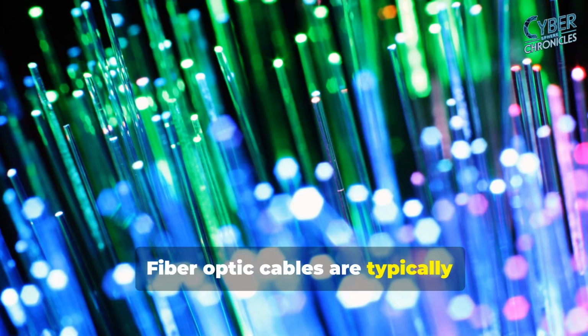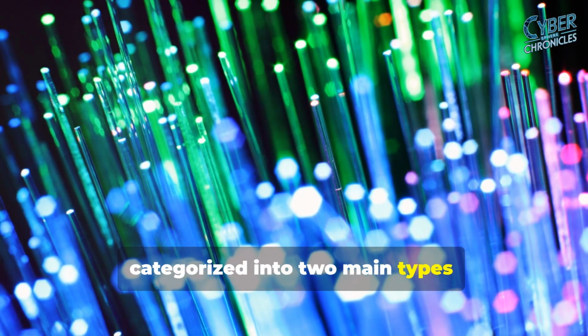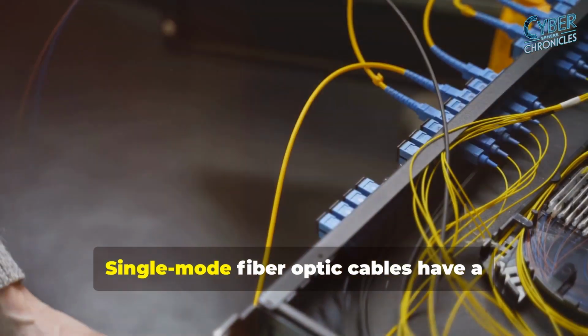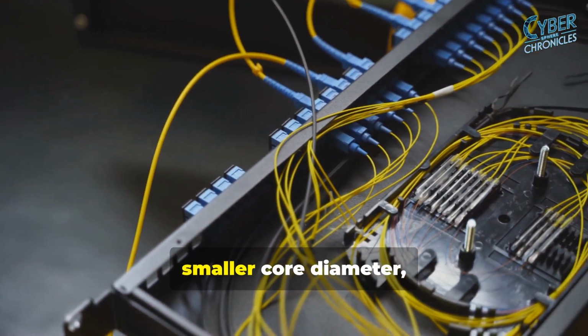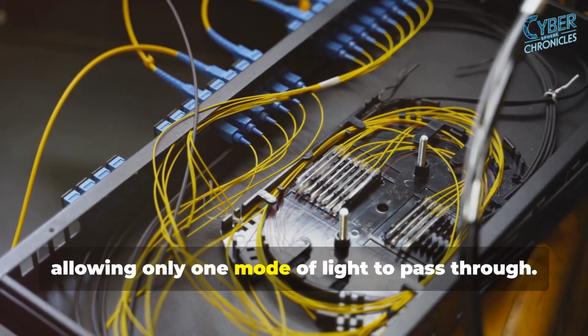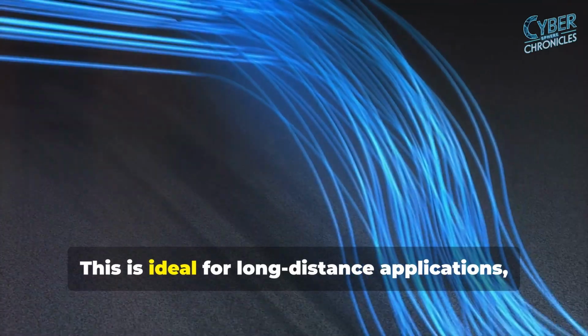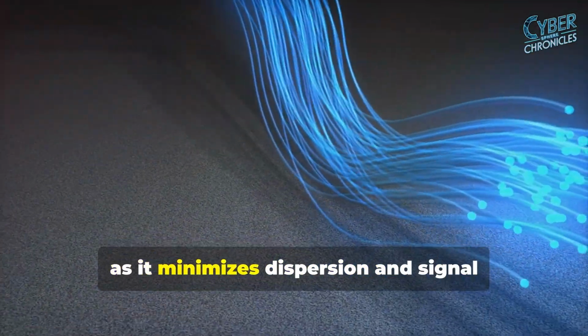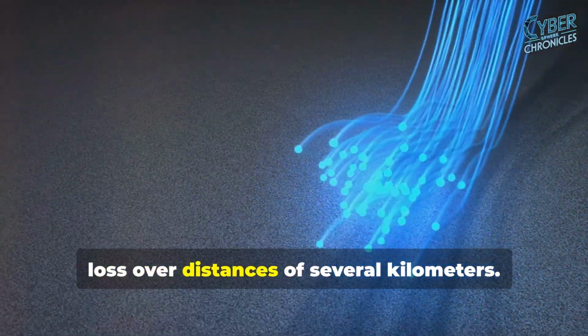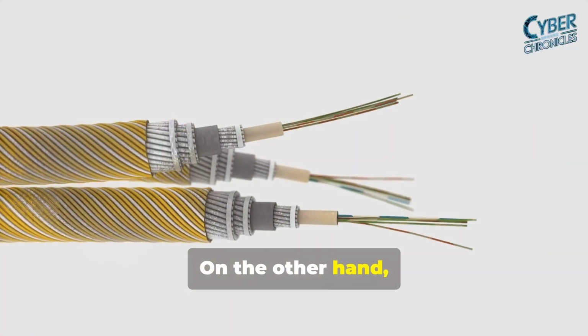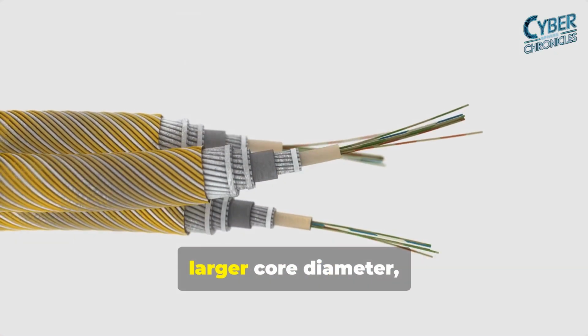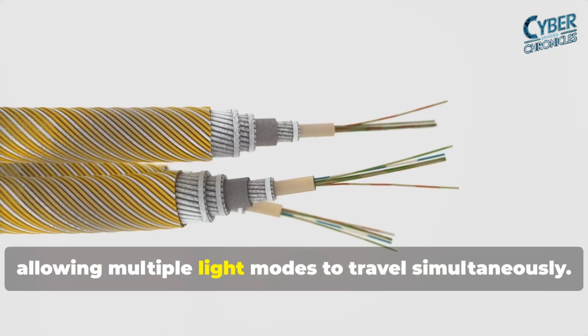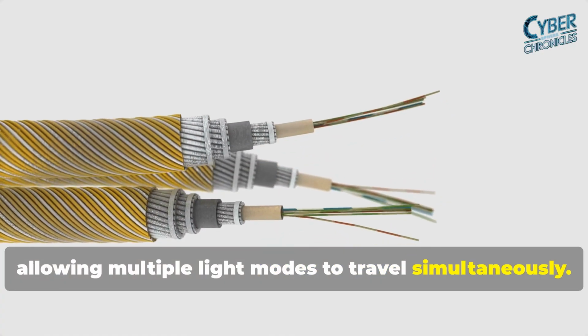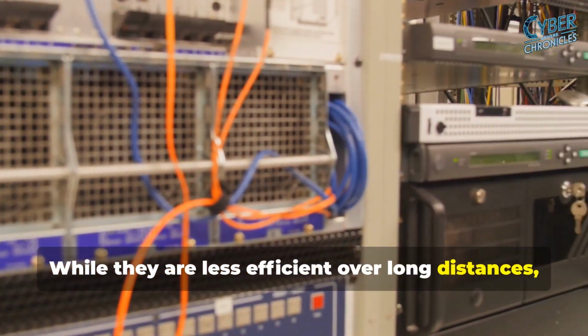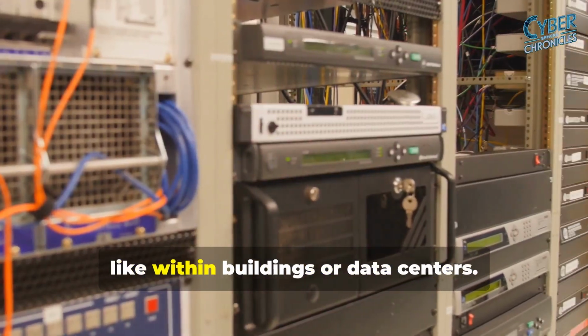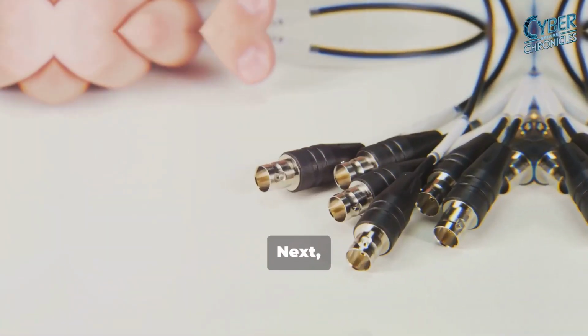Fiber optic cables are typically categorized into two main types: single-mode and multi-mode. Single-mode fiber optic cables have a smaller core diameter, allowing only one mode of light to pass through. This is ideal for long-distance applications, as it minimizes dispersion and signal loss over distances of several kilometers. On the other hand, multi-mode fiber optic cables have a larger core diameter, allowing multiple light modes to travel simultaneously. While they are less efficient over long distances, they are perfect for shorter distances like within buildings or data centers.